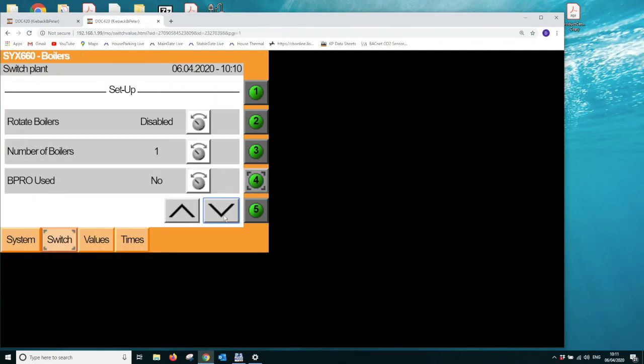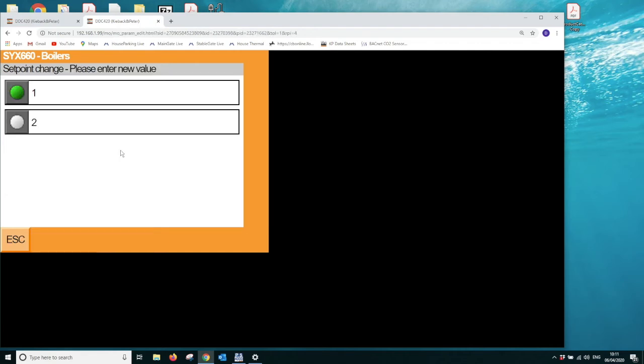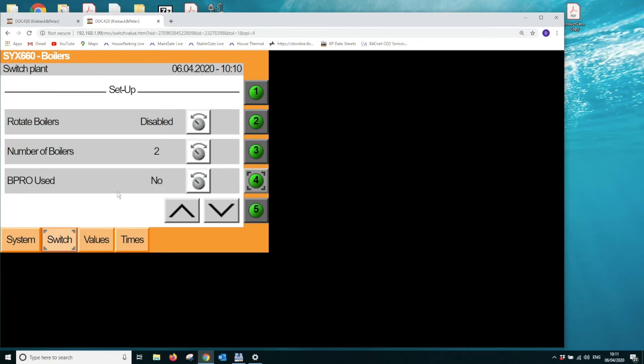We now click on system, and we click on boilers, and we tab down to the setup menu. This is where we can choose the number of boilers, and we click on 2. Because we've now got 2 boilers, the option to rotate the boilers becomes possible. It may be the case that you have 2 different styles of boilers, where one is a condensing boiler and one maybe isn't, because of upgrade plans or upgrade potential to the system.